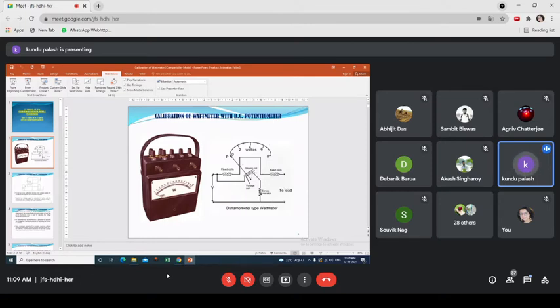The cross section of the movable coil is very small because it is called the potential coil, and the cross section of the fixed coil is large because it carries the load current. Wattmeters are generally used for the measurement of electrical power according to the scale. It has a scale at the extreme end, and the amount of the deflection theta is directly proportional to the amount of the power consumed by the load. There is no ferromagnetic part. That's why it is called the dynamometer type wattmeter, because the coils are not wound over any magnetic part, unlike in the case of moving iron instruments or moving coil instruments.